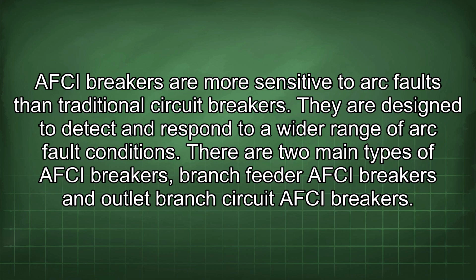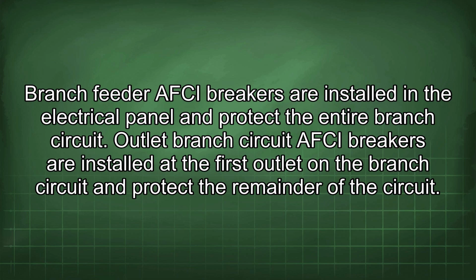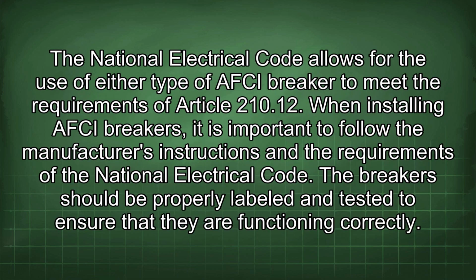AFCI breakers are more sensitive to arc faults than traditional circuit breakers. They are designed to detect and respond to a wider range of arc fault conditions. There are two main types of AFCI breakers: branch feeder AFCI breakers and outlet branch circuit AFCI breakers. Branch feeder AFCI breakers are installed in the electrical panel and protect the entire branch circuit. Outlet branch circuit AFCI breakers are installed at the first outlet on the branch circuit and protect the remainder of the circuit.